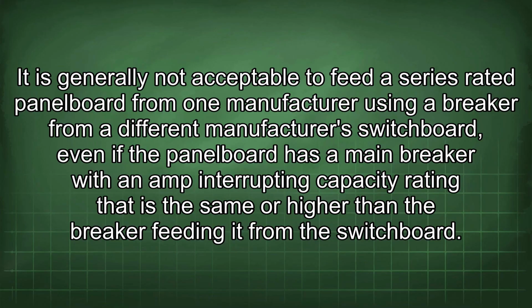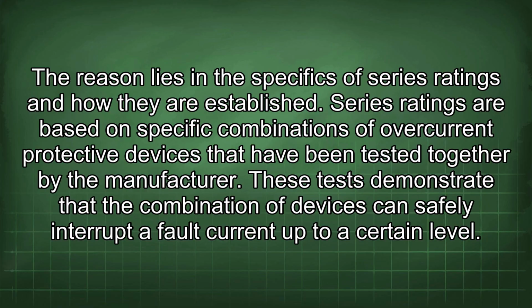It is generally not acceptable to feed a series-rated panel board from one manufacturer using a breaker from a different manufacturer's switchboard, even if the panel board has a main breaker with an amp interrupting capacity rating that is the same or higher than the breaker feeding it from the switchboard. The reason lies in the specifics of series ratings and how they are established.